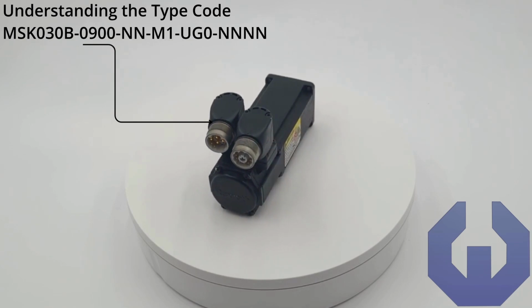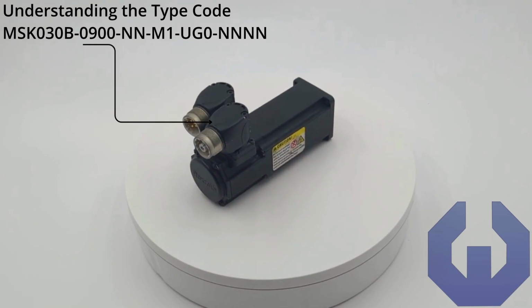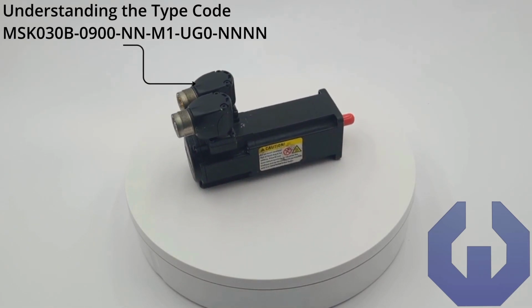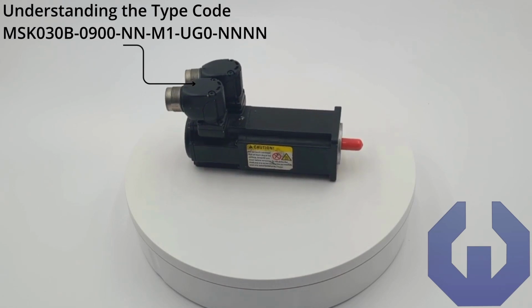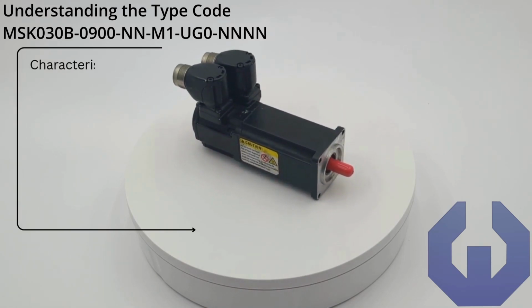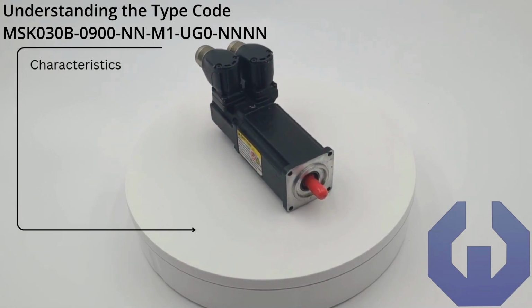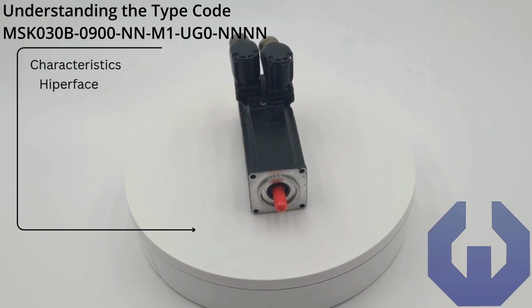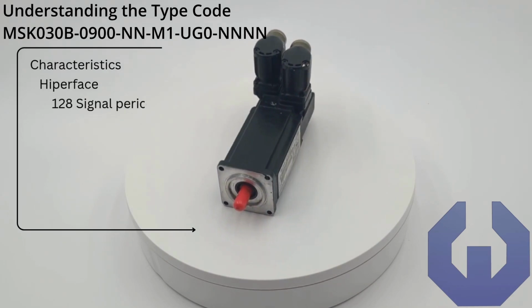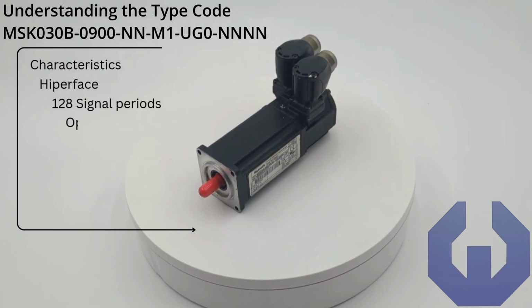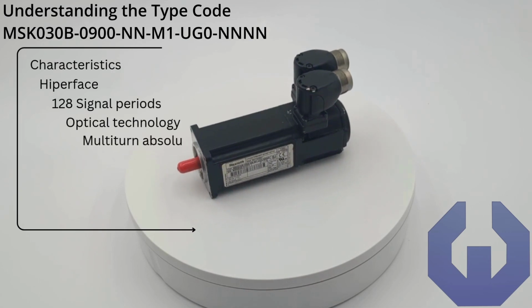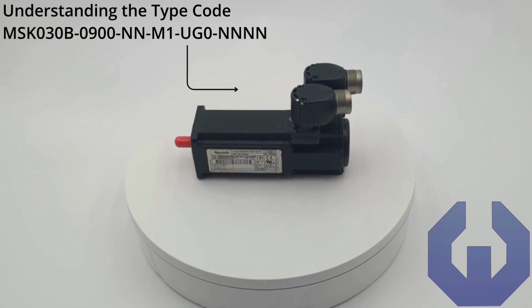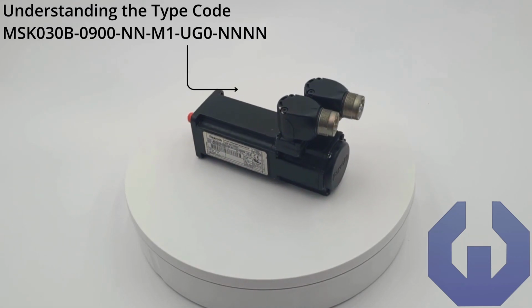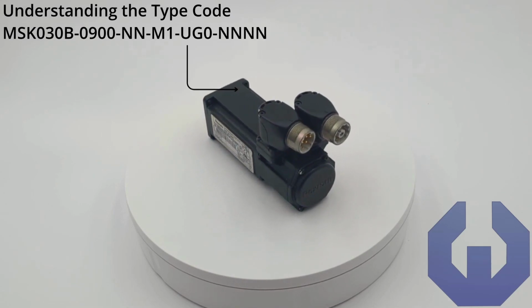0900 denotes the winding code for the motor is 0900. NN denotes the motor relies on natural convection for cooling. M1 denotes several characteristics about the MSK encoder. Its interface uses HIPERFACE, its resolution is 128 signal periods, it relies on optical technology, and it turns via multi-turn absolute. U denotes the encoder connector is rotatable, up to 240 degrees.